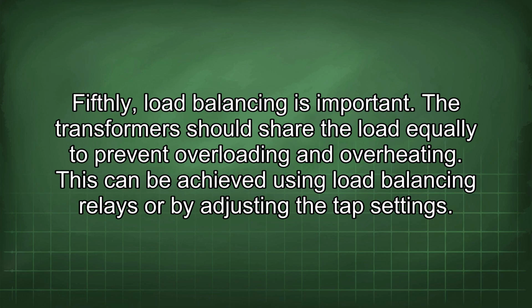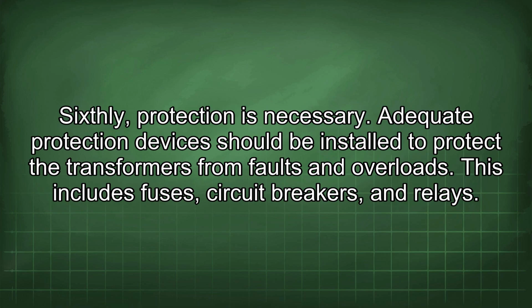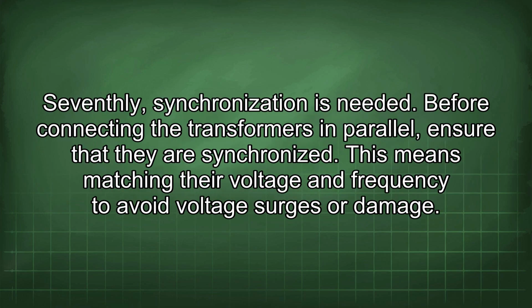Fifthly, load balancing is important. The transformers should share the load equally to prevent overloading and overheating. This can be achieved using load balancing relays or by adjusting the tap settings. Sixthly, protection is necessary. Adequate protection devices should be installed to protect the transformers from faults and overloads. This includes fuses, circuit breakers, and relays. Seventhly, synchronization is needed. Before connecting the transformers in parallel, ensure that they are synchronized. This means matching their voltage and frequency to avoid voltage surges or damage.